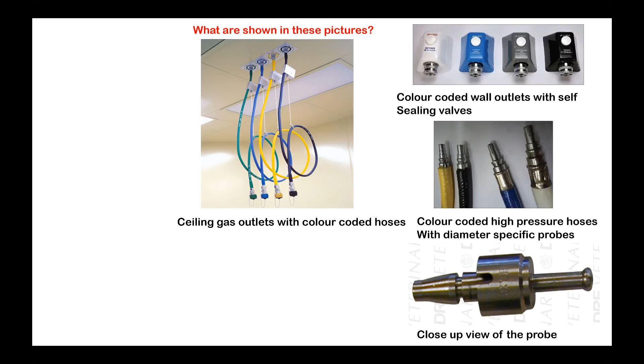And what is this? Index system. This is the pin index block for connecting the hose to the machine. So in the hanger yoke, instead of the cylinder, if you are fixing these hoses, then the same pin index mechanism will be there. Pin index for oxygen and nitrous oxide. This is the whole pin index block, which can be fitted into the hanger yoke. What is this? If you don't fix it on the hanger yoke, on the back of the machine you can fix this, the diameter index safety system. You can just insert it and then thread that screw into position. So this is the oxygen and nitrous attached to the back of the machine and not on the hanger yoke.